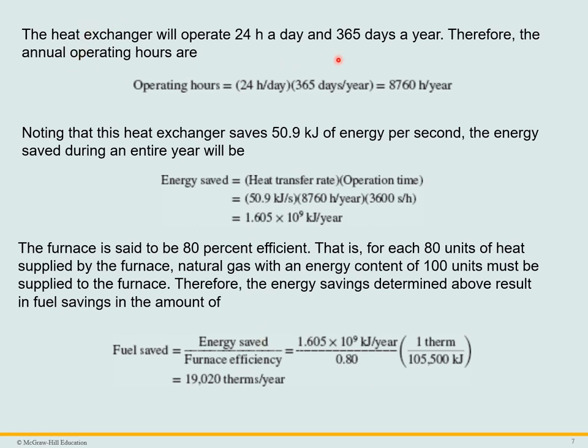Since this heat exchanger will operate 24 hours a day, 365 days a year, that's 8,760 hours per year. Knowing that this heat exchanger saves 50.9 kJ/s of energy, we can find the energy saved per year by multiplying by the number of seconds in a year using the appropriate conversion factors. The furnace is 80% efficient, so for each 80 units of heat supplied by the furnace, natural gas with an energy content of 100 units must be supplied.